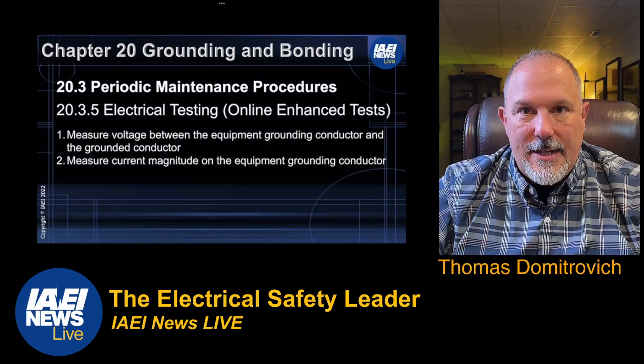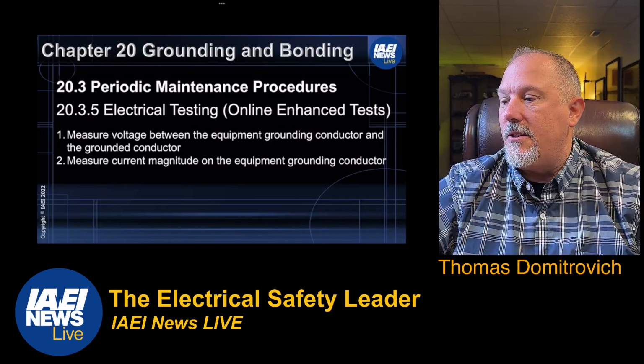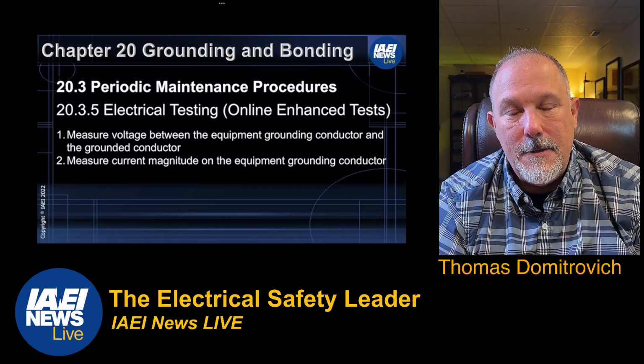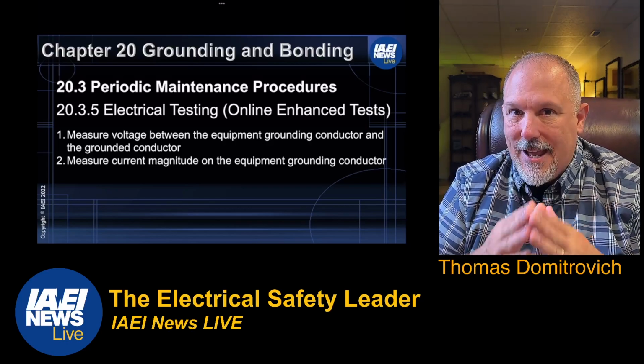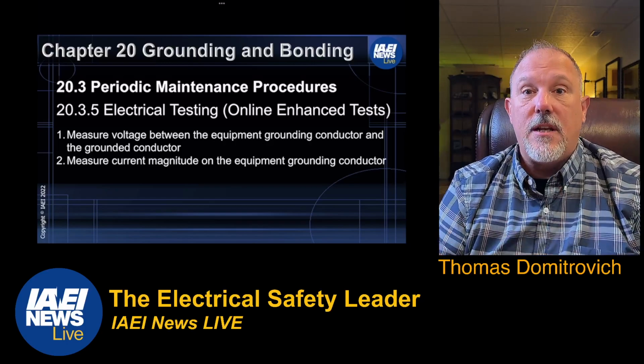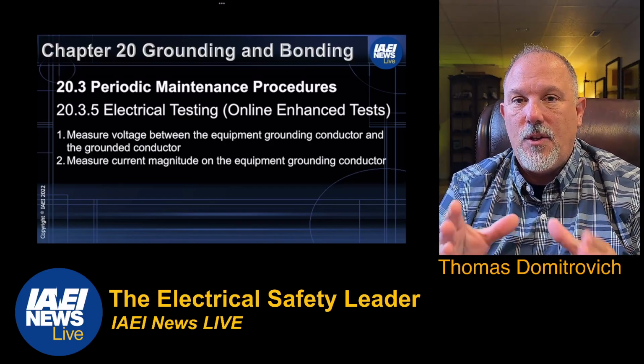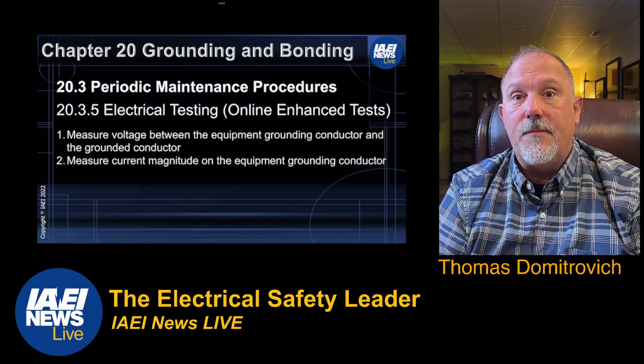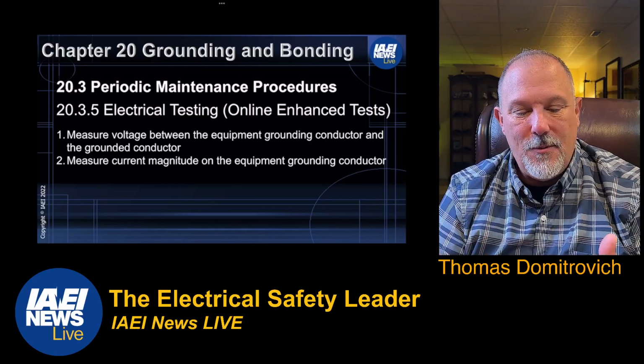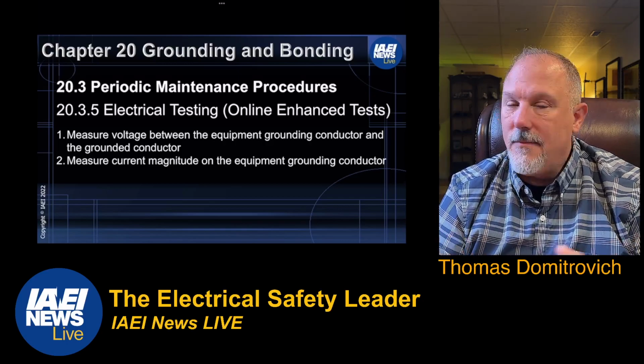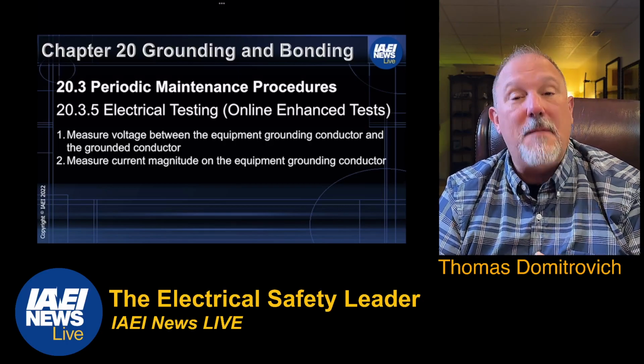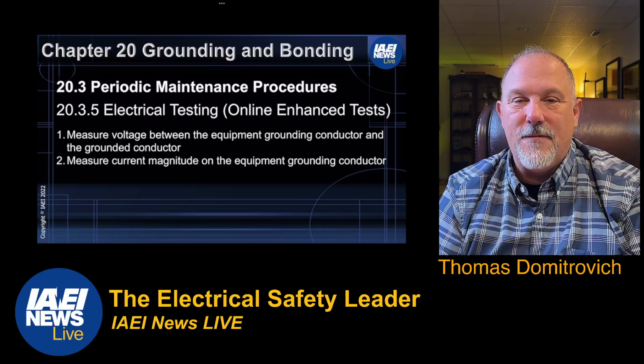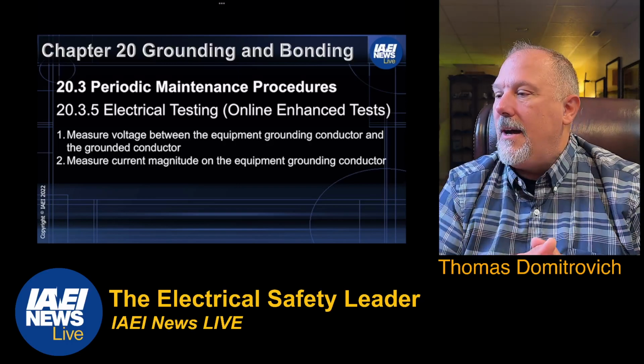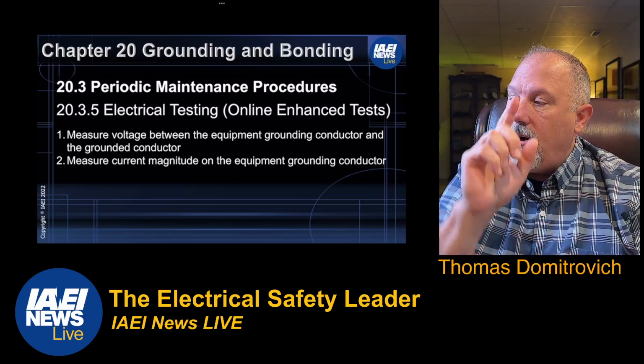Now, these are, again, online enhanced tests. Measure the voltage between the equipment grounding conductor, and measure the current magnitude on the equipment grounding conductor. An enhanced test is not a standard test, not something you do on every single grounding and bonding termination. You do this when you suspect something, when you had a fault on the system, or you have something going on in your system that you think might be related to grounding and bonding, which for obvious reasons, people think everything is related to grounding and bonding. It's that mystery, right? So again, these are online enhanced tests. Chapter 8, 8.3.